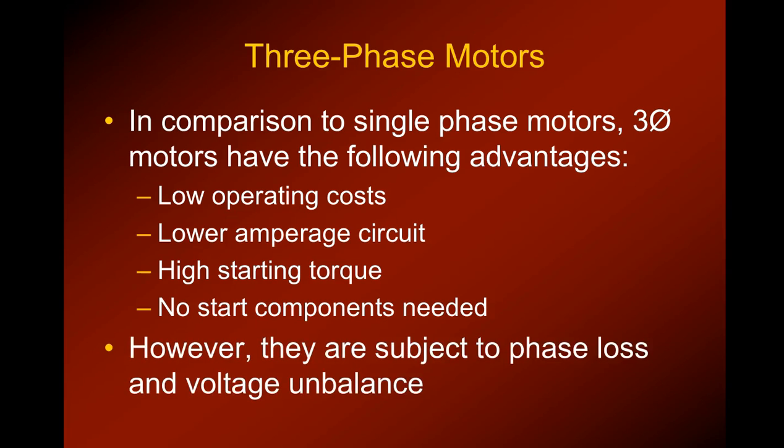But there is a problem that you may run into from time to time with three-phase motors, and that's they're subject to a phase loss and voltage unbalances. What happens is when there's three legs of power coming in, sometimes the incoming power will lose a leg of the three-phase or it will become unbalanced, meaning that the voltage of the three legs of power coming in are not the same. I had one of my students that ran into this not too long ago, where there was a hundred volt difference between the incoming voltages on one of the legs, and it burned up a large three-phase motor. So you should always be checking for voltage unbalance in a three-phase motor situation.